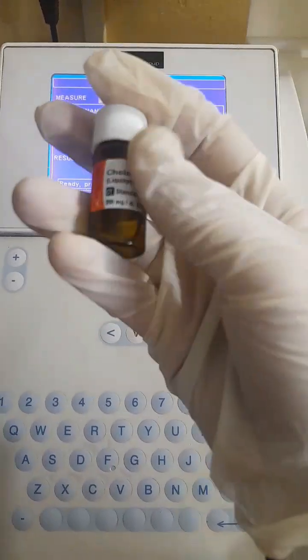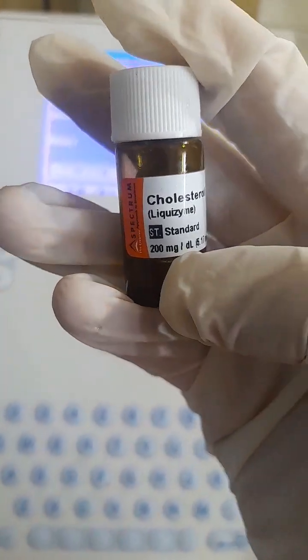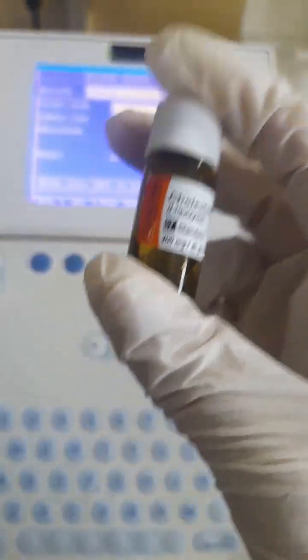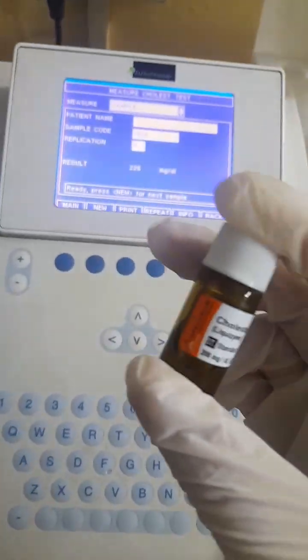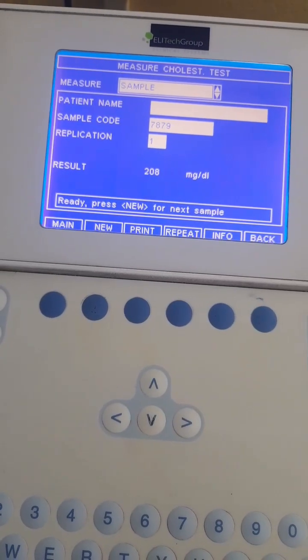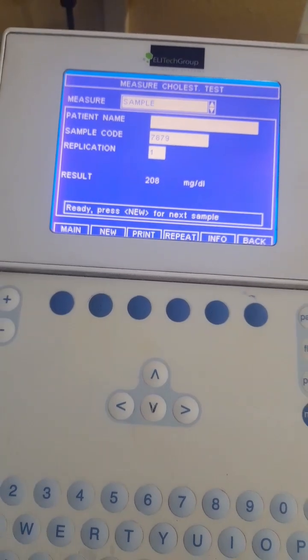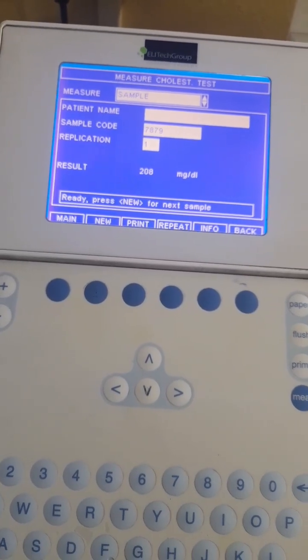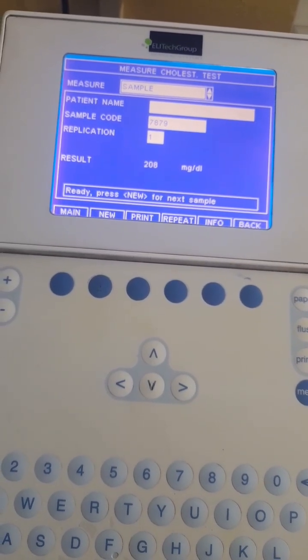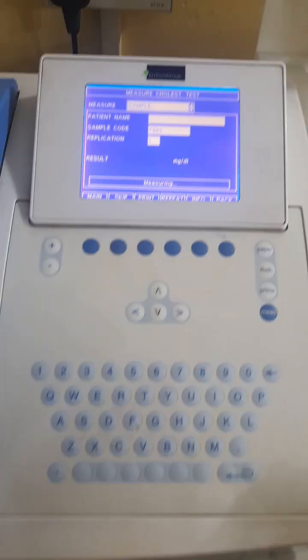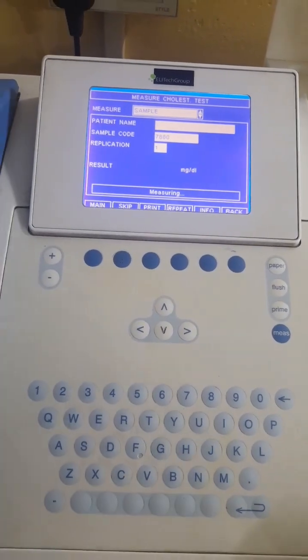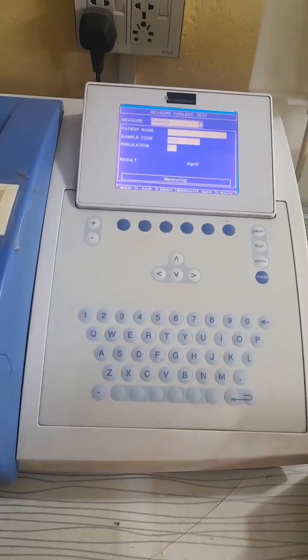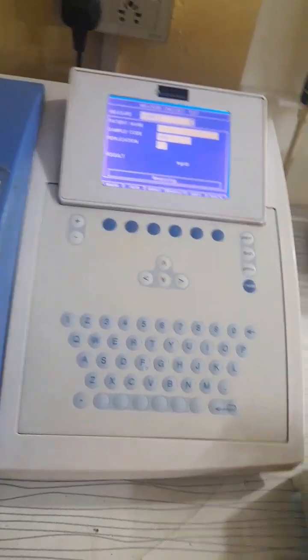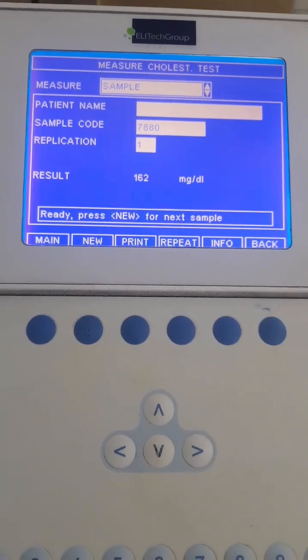Now I have to recalibrate the instrument. Then I have to put the sample again. After the recalibration, the standard is showing 208, which is also not acceptable. Now I have to recalibrate the instrument again. After the recalibration, now I am going to put the sample. It will take a very short time, as I just put the sample, and the result is 162, which is acceptable.